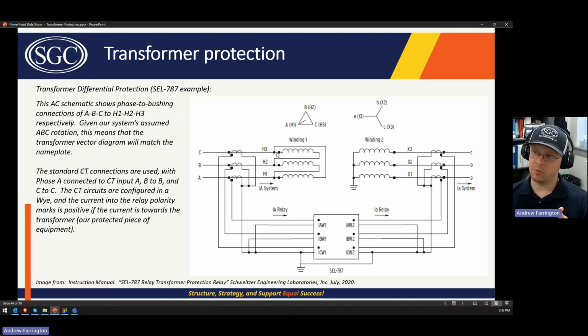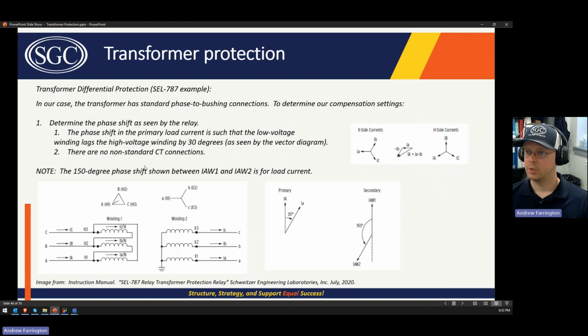In our application, we only have the delta winding. We don't have a source of zero sequence current on the high side, so we can use a setting of 0. Okay.